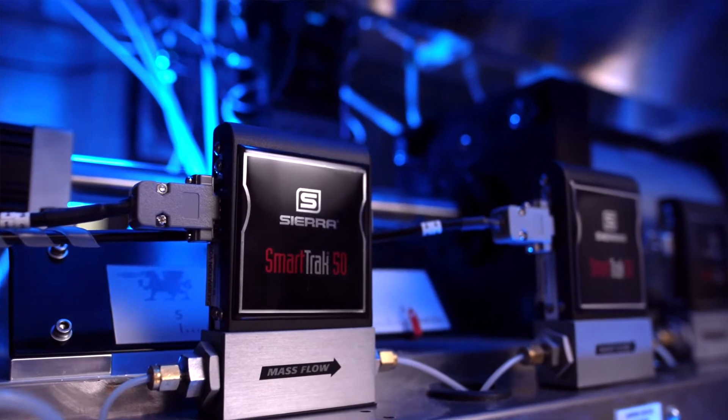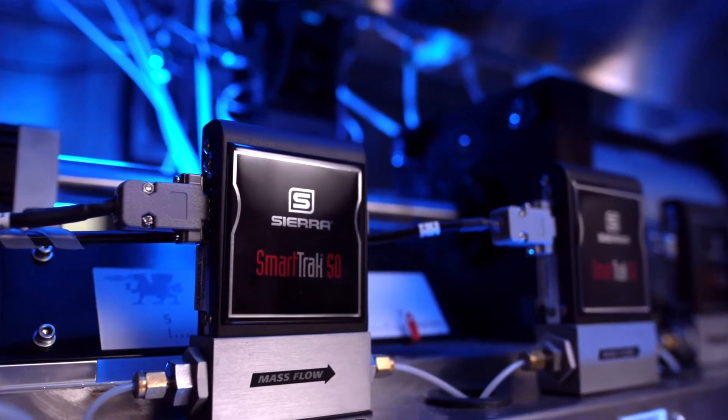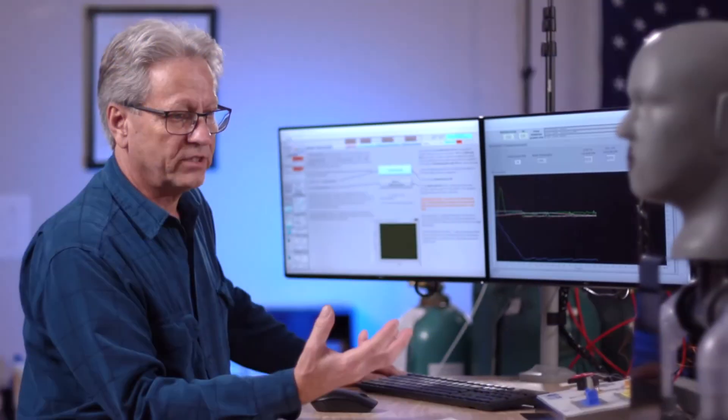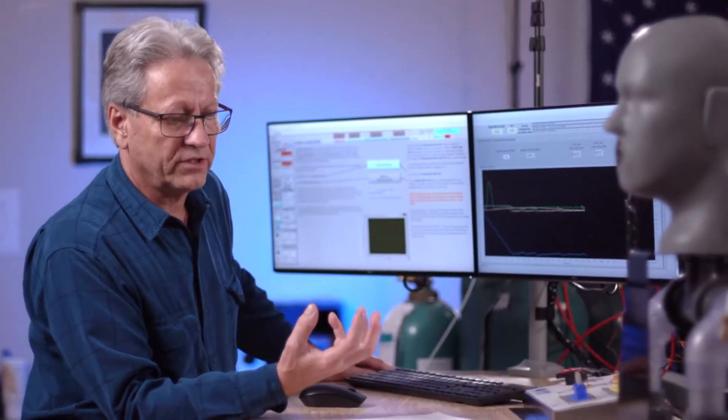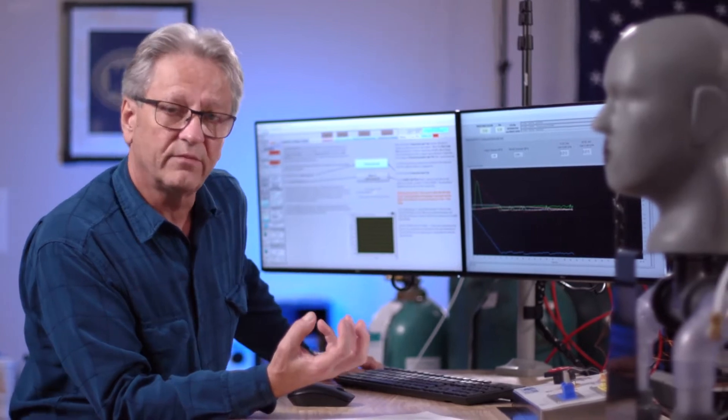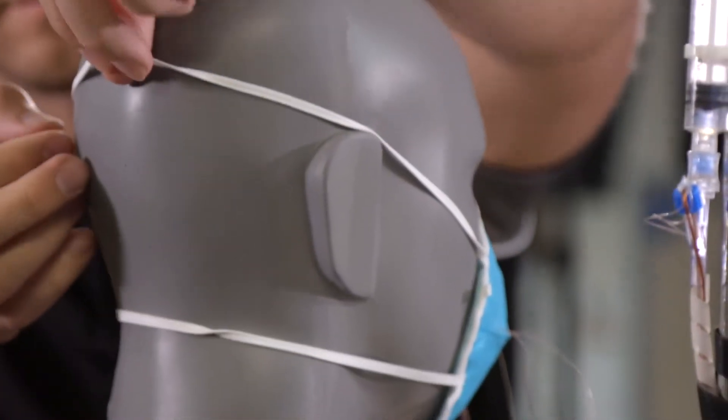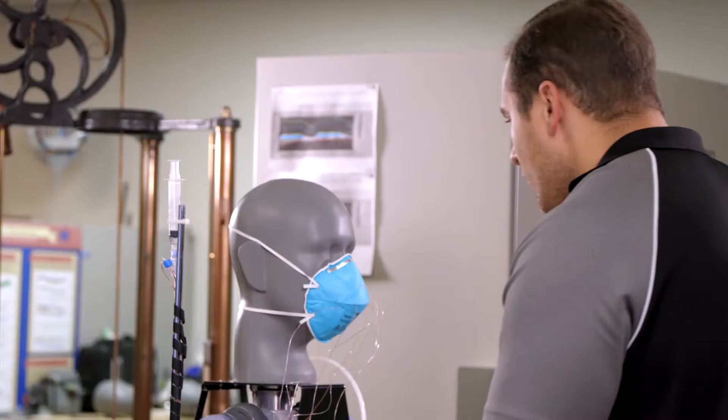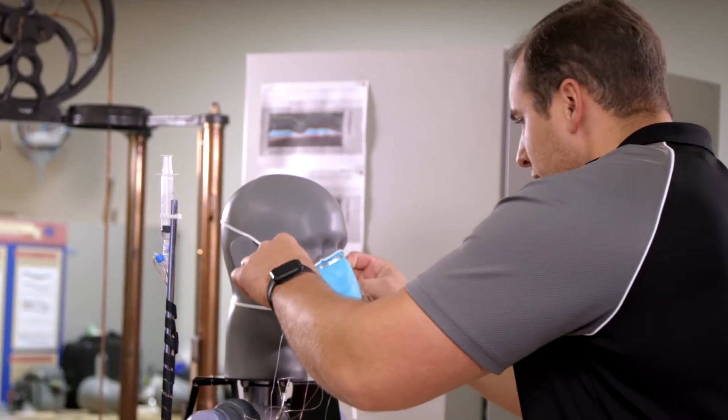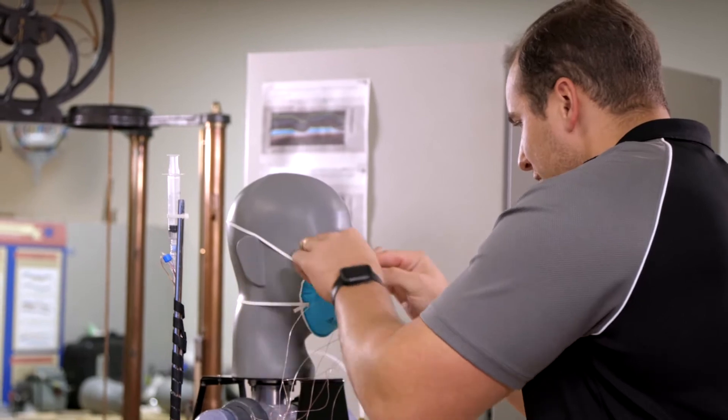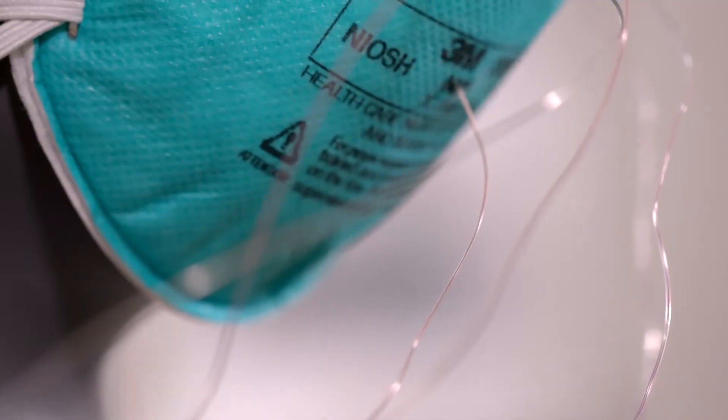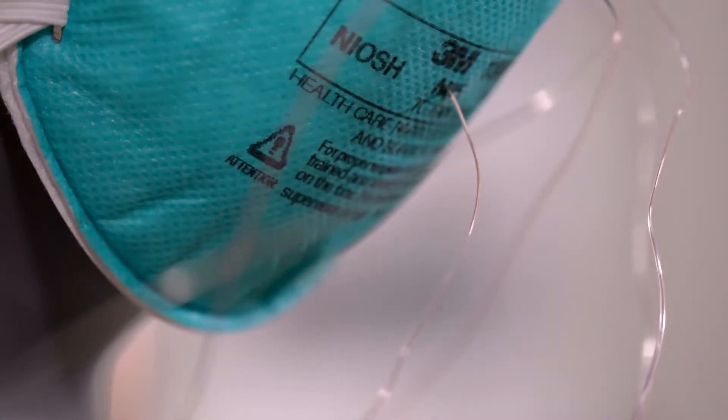We use mass flow controllers to monitor the inward leakage rate. The vacuum test verifies that the system is tight. The positive leak test allows us to use a soap solution in order to find a leak in either our system or the apparatus under test.